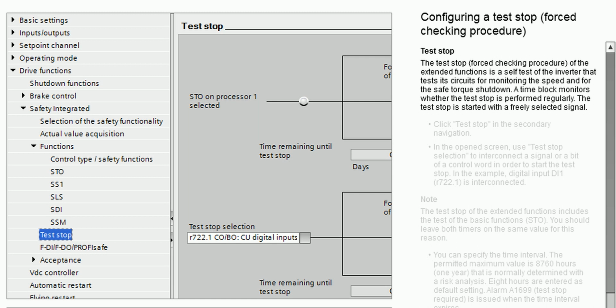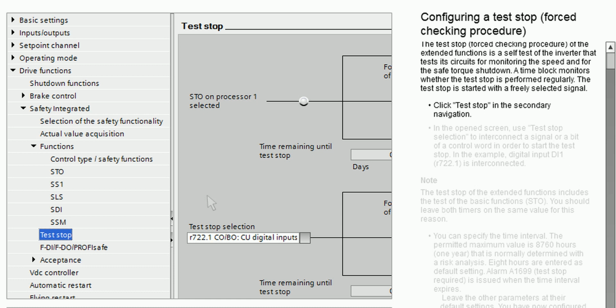Test stop. The test stop, force checking procedure, of the extended functions is a self-test of the inverter that tests its circuits for monitoring the speed and for the safe torque shutdown. A time block monitors whether the test stop is performed regularly. The test stop is started with a freely selected signal. Click Test Stop in the secondary navigation.